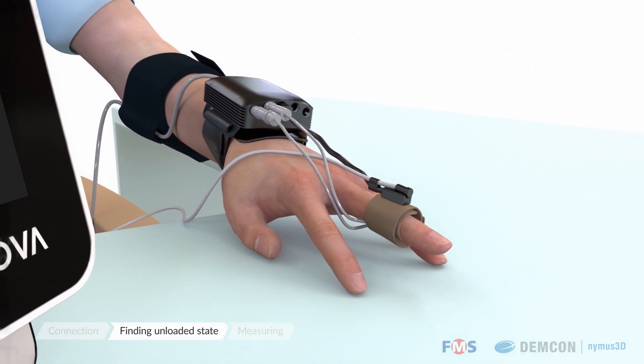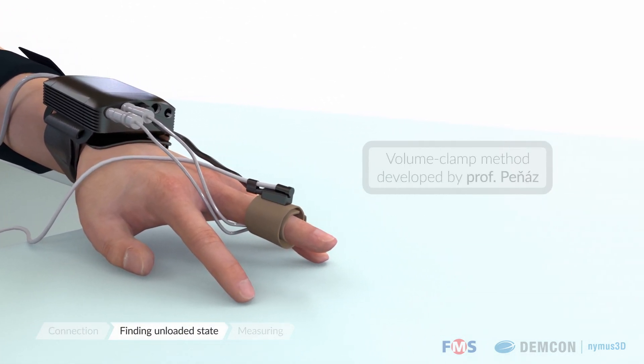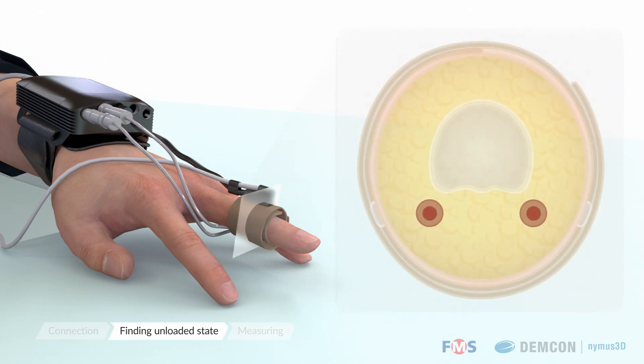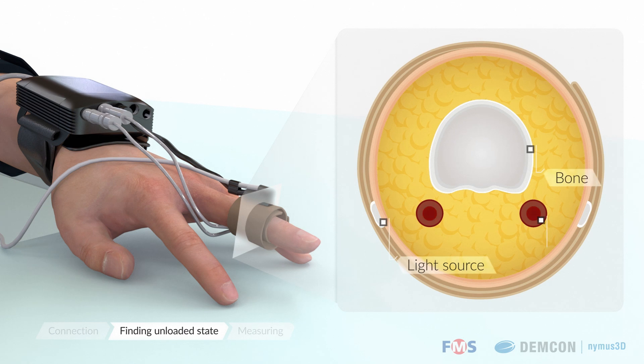The system functions via the volume clamp method developed by Professor Peňáz in the 1970s. An inflatable cuff exerts pressure on the finger, while a light sensor monitors the diameter of the finger arteries throughout the blood pressure pulse cycle.